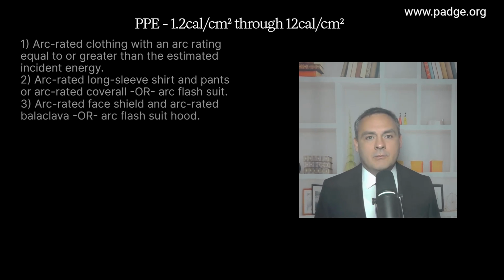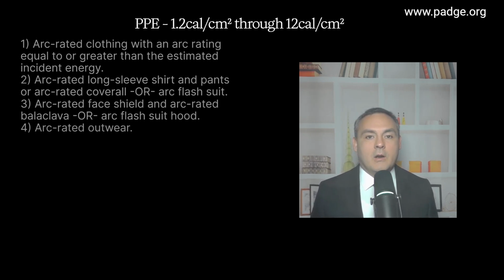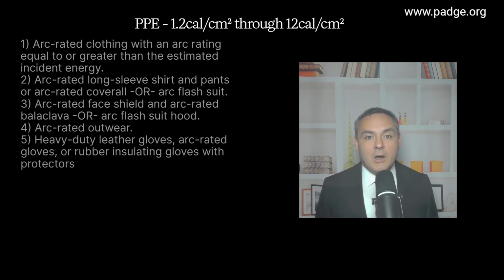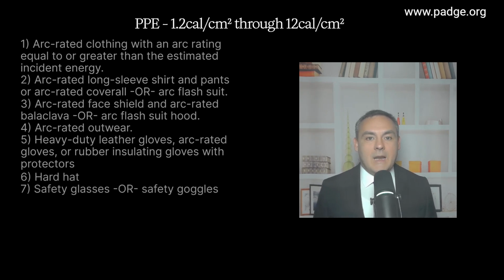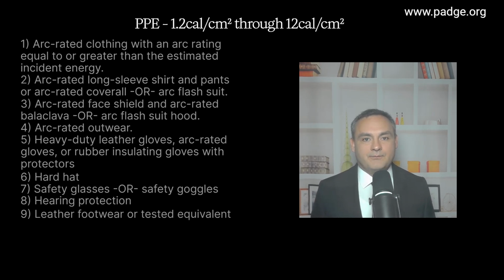Arc-rated face shield and arc-rated balaclava or arc flash suit hood. Arc-rated outerwear as needed, high visibility option. That's an example. Heavy-duty leather gloves, arc-rated gloves, or rubber insulating gloves with protectors. Hard hat. Safety glasses or safety goggles, hearing protection, leather footwear or tested equivalent.